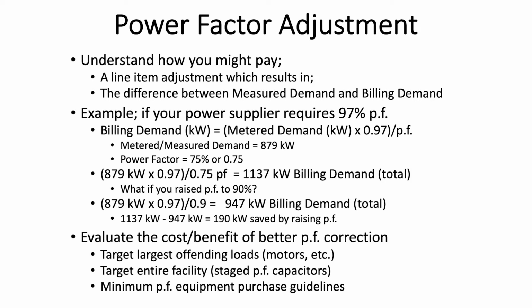So why don't I necessarily want it to get to 100%? In a perfect world, I would probably want to. But I don't need to. I only need to get it to the level where they're going to ding me or above. Sometimes the best cost-benefit ratio is lower than that level. So you have to work with your power factor people that have done the study, what the costs are, things like that. Then you evaluate the cost-benefit of better power factor correction.